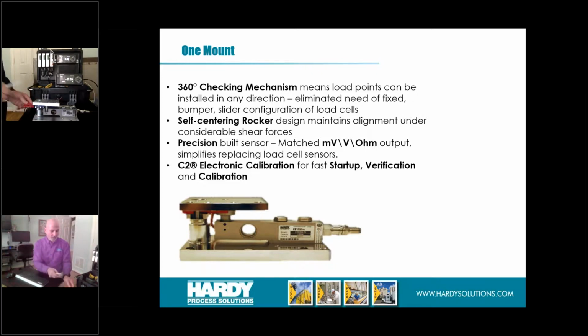If you've got vibration in one plane, you'd put the bumper on that leg. For vibration on another leg going a different direction, you'd put the slider there. The fixed one would be on the leg at the center of the axis it was rotating around. This device, because of the floating head, eliminates the need for fixed bumper and slider. You just buy 4 of these load cells, and they go on any leg, so you don't have to guess which way the vibration is going.